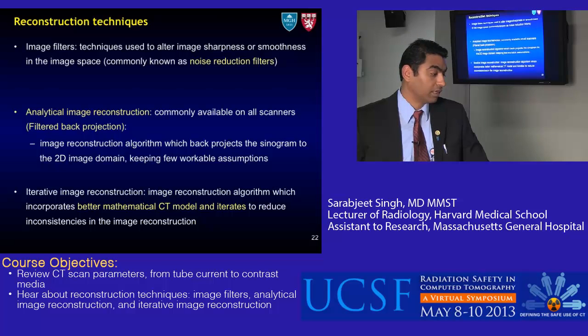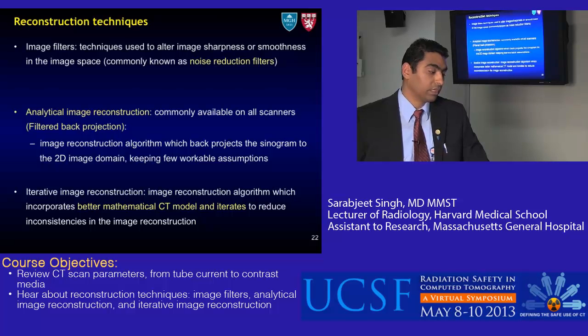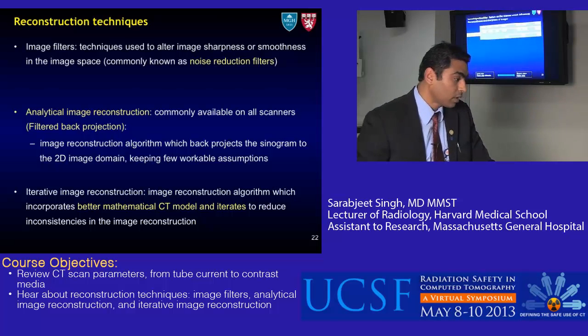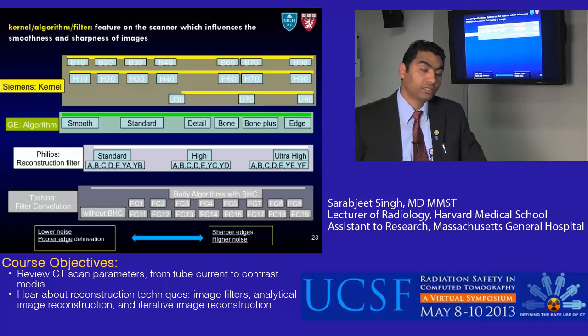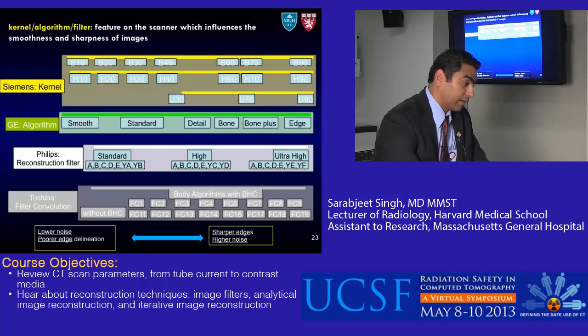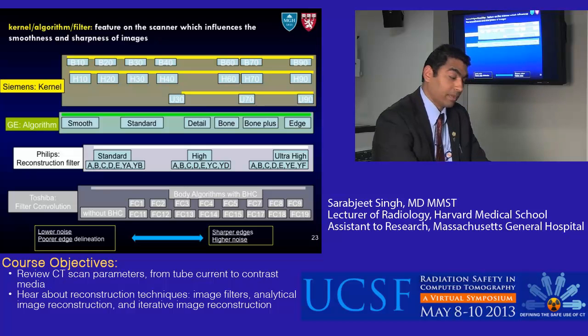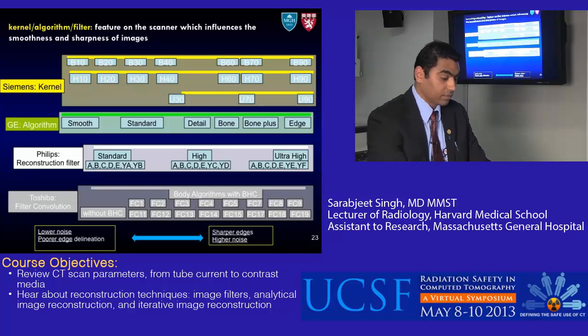Newer iterative image reconstruction techniques incorporate better mathematical CT models and iterate in loops to reduce inconsistencies in image reconstruction. Another scanner feature is the kernel, commonly known as algorithms or filters. This feature influences the smoothness or sharpness of the image and is typically applied before the image is reconstructed. Siemens has a set of kernels, GE calls them algorithms, and Philips calls them reconstruction filters.